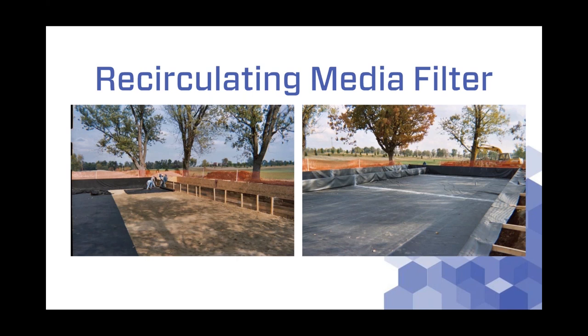What we've learned is that sand media often is very hard to get with proper sizing, and it's usually not clean depending on where it comes from and how well it was washed. Sand filters get plugged over a short period of time, and then all the distribution piping has to be removed, the sand has to be removed and disposed of, new sand put back in, and the distribution pipe reconnected. So not a great plan — they don't have a long lifespan.